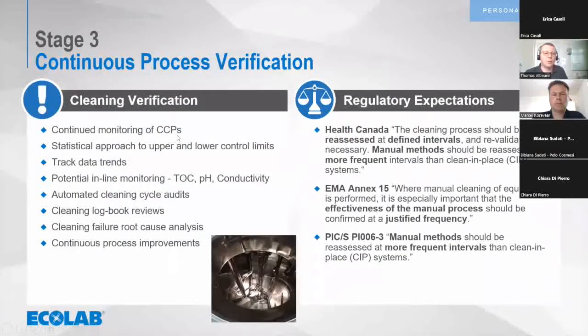That means we have understood our critical control points. Is the temperature important? Is the cleaning time? Is the concentration important? And we are tracking that by conductivity, by run times of pumps, by pressure indication, or whatever. We track that and even make data analysis to see trends. So if a process always runs at 2 bars at the spray balls, and then suddenly there is 5 bars, maybe there is a blockage somewhere, and the cleaning might be more ineffective. But we have to identify that there is a difference.